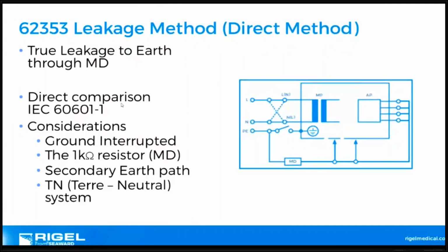Comparison to 60601 does have the single fault condition of the earth open, and we can reverse live and neutral. Only applicable to TN systems, and this is something that I need to stress and go over later. TN systems and measuring earth leakage currents is one of the often misunderstood concepts of electrical safety. We'll discuss that later on.